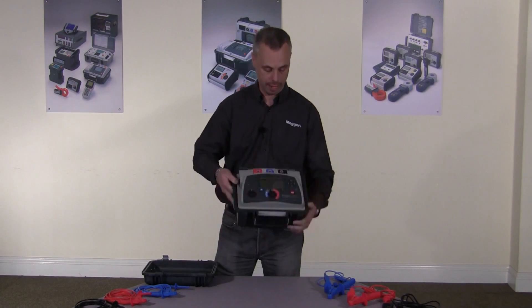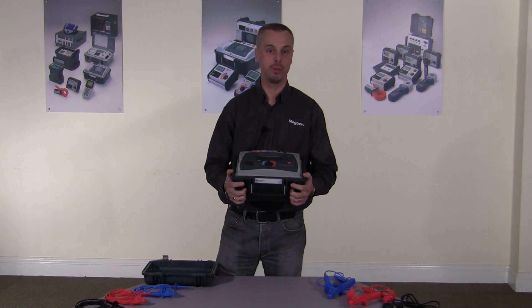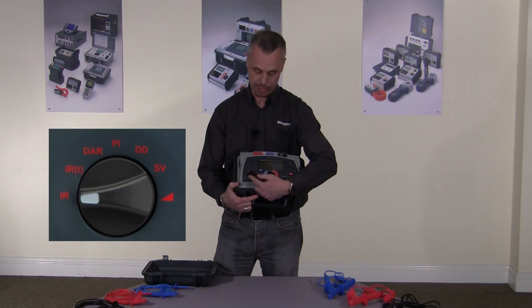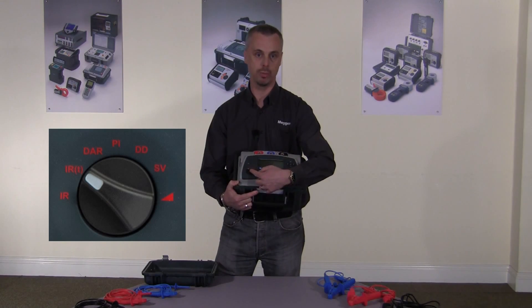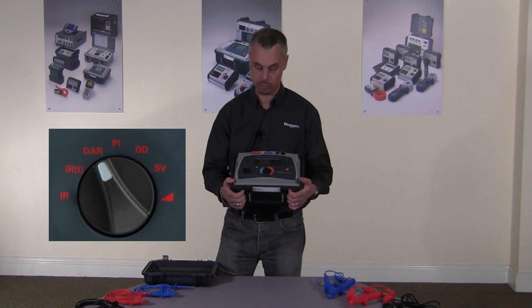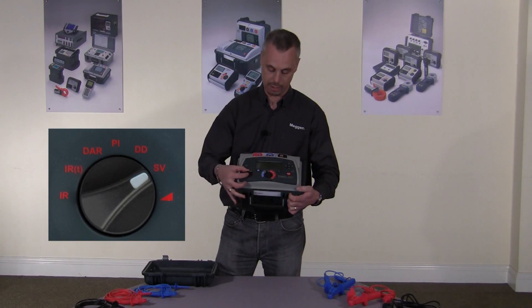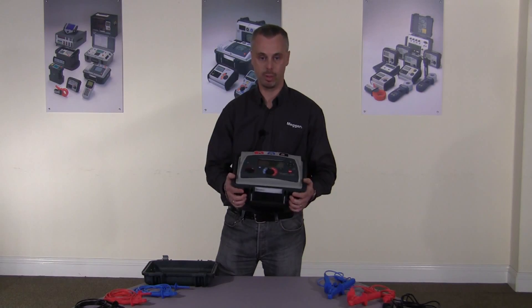The MIT 525 can measure up to 10 teraohm. The 10 kV version, the MIT 1025, can measure up to 20 teraohm. Both instruments are fully diagnostic. On the mode selection switch we have an IR test — insulation resistance — a timed IR test which will stop automatically at the time you set, the DAR which is dielectric absorption ratio, the polarisation index test, dielectric discharge test, step voltage test, and finally the ramp test. So it's fully diagnostic — all the tests you require are on the product.